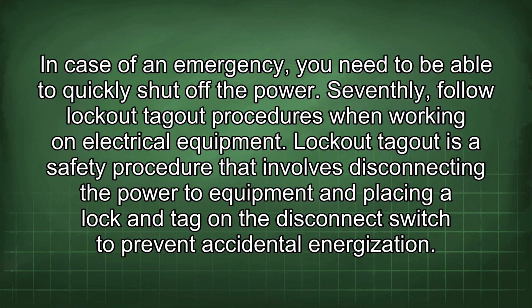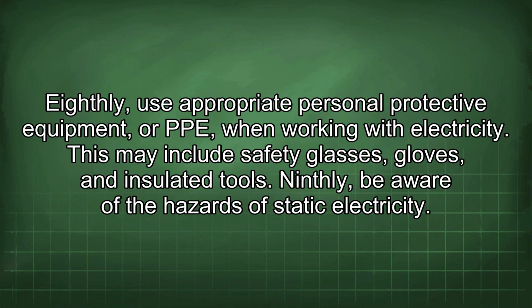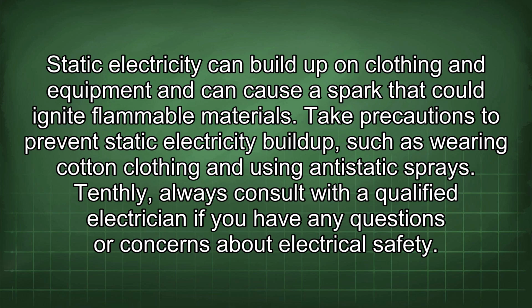Seventhly, follow lockout-tagout procedures when working on electrical equipment. Lockout-tagout is a safety procedure that involves disconnecting the power to equipment and placing a lock and tag on the disconnect switch to prevent accidental energization. Eighthly, use appropriate personal protective equipment, or PPE, when working with electricity. This may include safety glasses, gloves, and insulated tools. Ninthly, be aware of the hazards of static electricity. Static electricity can build up on clothing and equipment and can cause a spark that could ignite flammable materials. Take precautions to prevent static electricity buildup, such as wearing cotton clothing and using anti-static sprays. Tenthly, always consult with a qualified electrician if you have any questions or concerns about electrical safety.